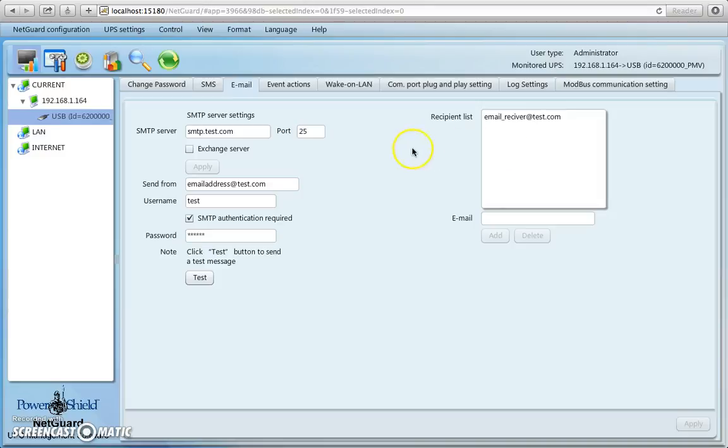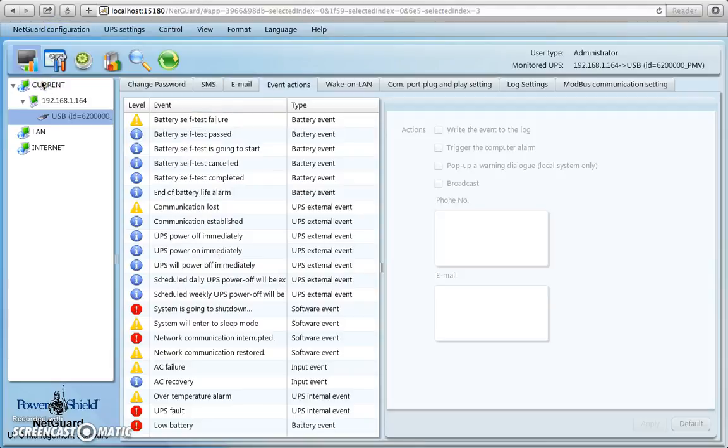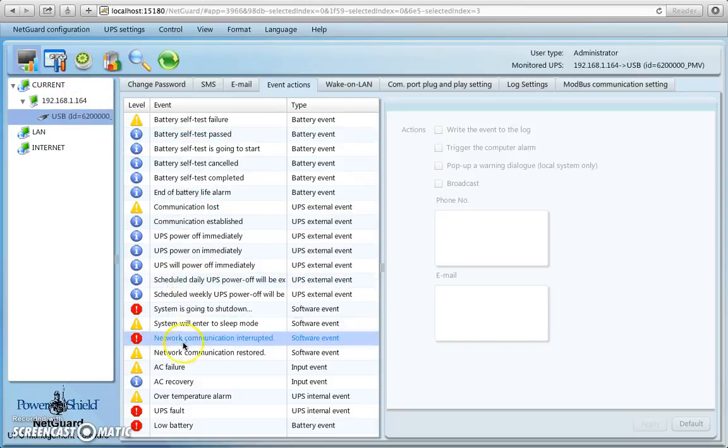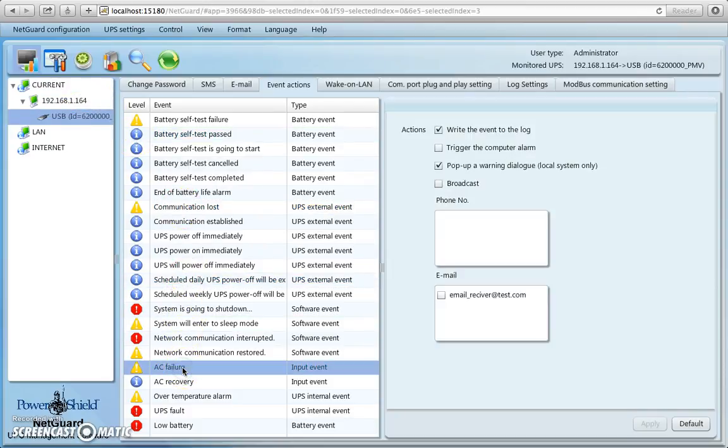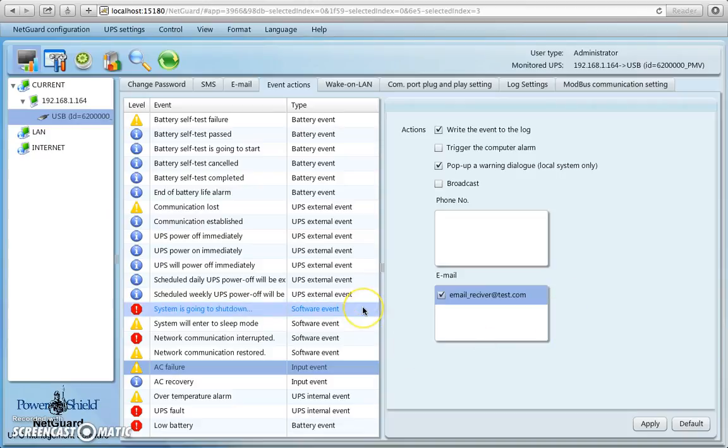Now, if you want to know what actually can trigger an email, what kind of event will trigger an email, well you go down to the event actions window, and you can set up various things. For instance, I always like to go down to an AC failure, and I click on AC failure, and if I have an AC failure, I want this recipient email to receive a notification email to say that I've lost power from a utility company. And that's pretty well all it is.